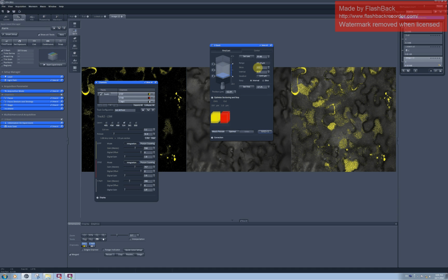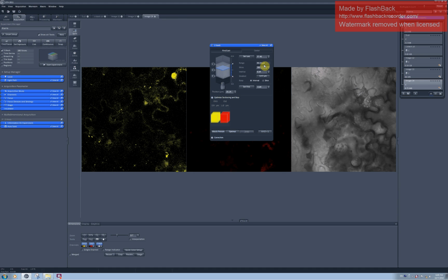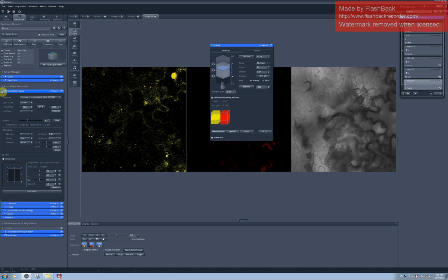It quite dramatically increases the number of slices. High number of optical slices will increase the time required for Z-stack scanning. Prolonged exposure to laser light might lead to photobleaching of a fluorophore and also additional artifacts caused by phototoxicity. So one should be careful about it. One can increase the speed of scanning by decreasing the number of slices and also by tweaking parameters in the acquisition mode to decrease the scanning time for each individual optical slice.